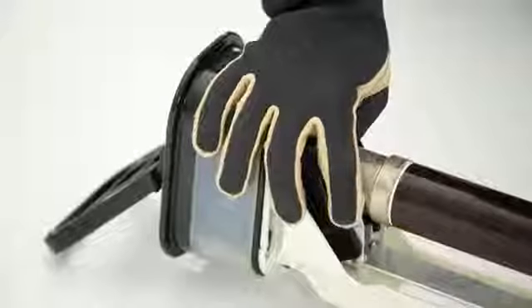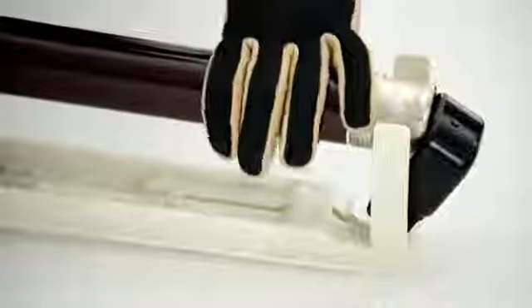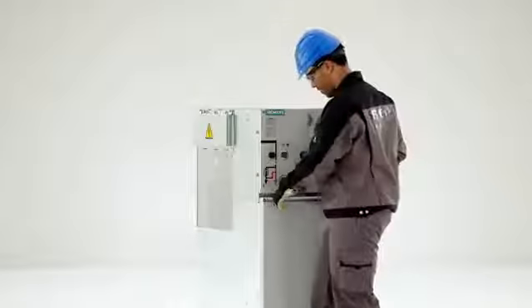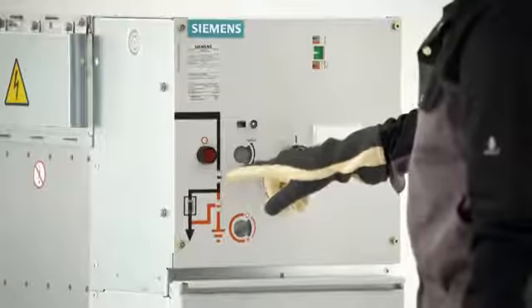Even where there is pollution and humidity from outside, the dielectric strength is not affected. After replacing the fuse, the cover can only be closed if the fuse slides have also properly latched in. And only then can the feeder be de-earthed and reclosed. So switching is both innovative and safe.